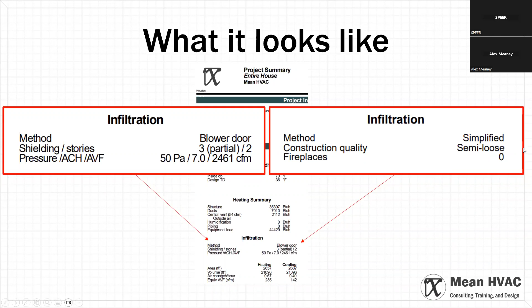So FYI, one of the things I look for when I see a load calc is when I have a house that's in this tightness range or above. This is a little bit of a coin flip for me, but if you're at semi-tight or tight, how should I have ventilation, right? The old school rule, which we used for 20 years before we started getting aggressive about our ventilation standards around 2010, was a third of an air change per hour natural. And natural air change rate is a 4 Pascal air change rate. That's not this number, right? It's a different number. This is the natural, this is the actual here.